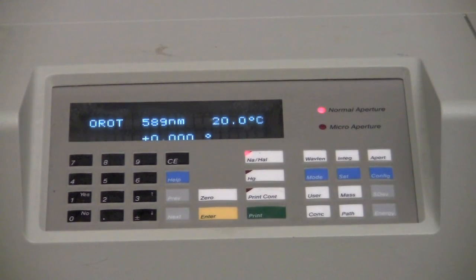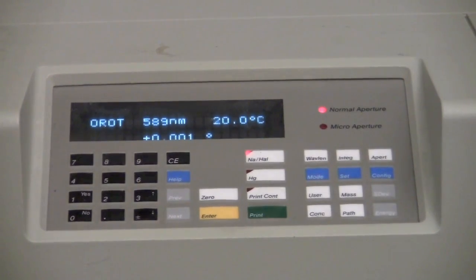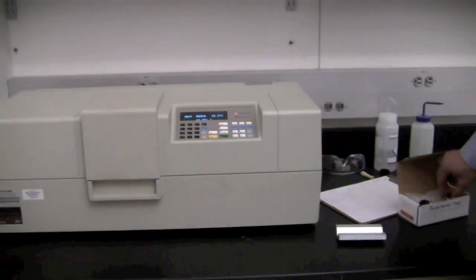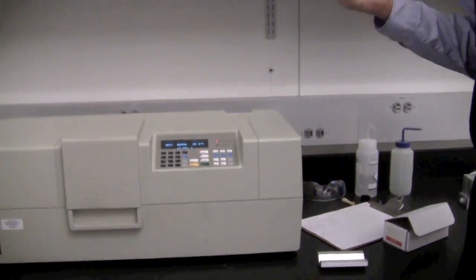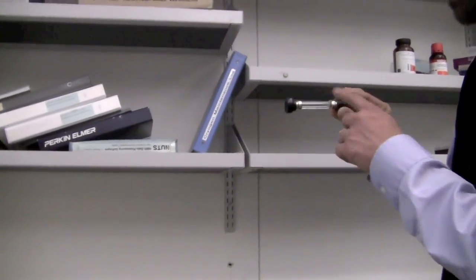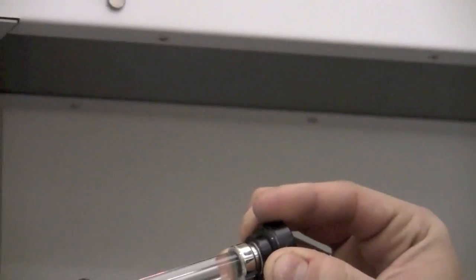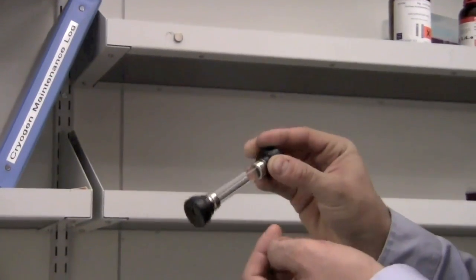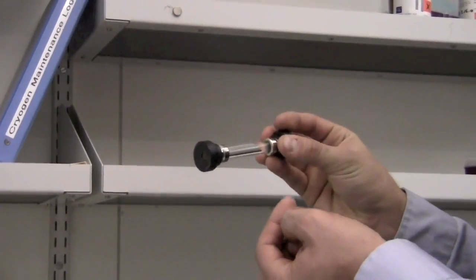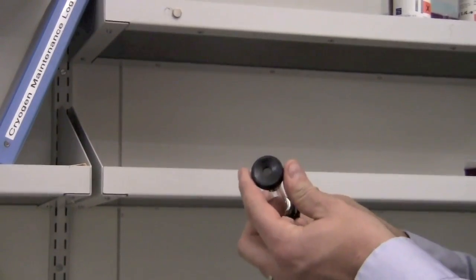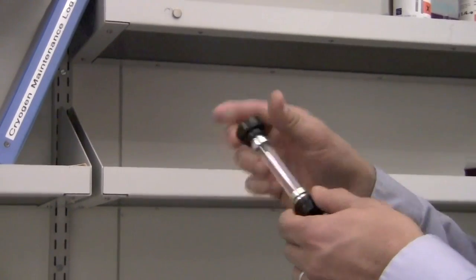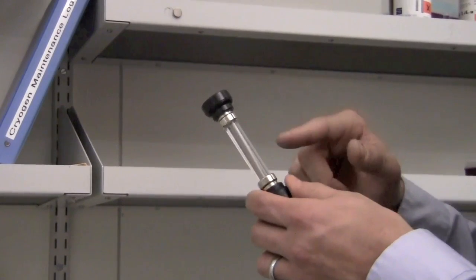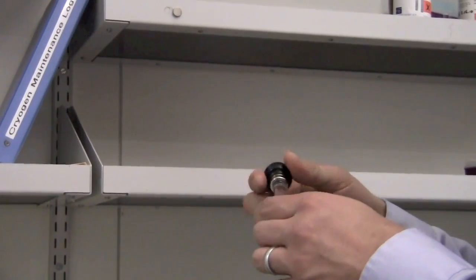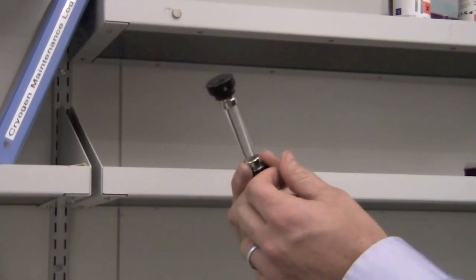Okay, so to measure the rotation of a sample, you need to put it in a polarimeter cell. The polarimeter cells are 10 centimeters long. There are different diameters of cells. This one holds 10 milliliters. Larger ones will allow more light throughput and a more accurate measurement, but of course they use more sample. So you'll want to fill the cell, and make sure there's no debris in there and no bubbles in the cell.